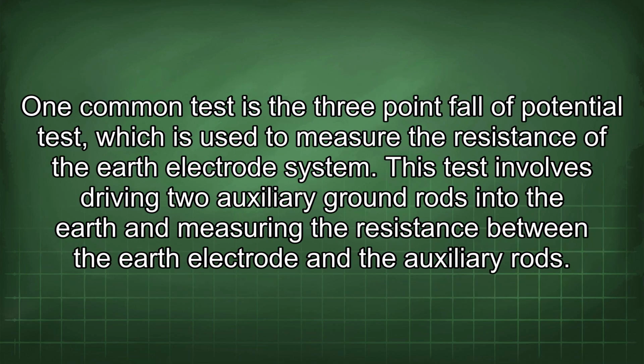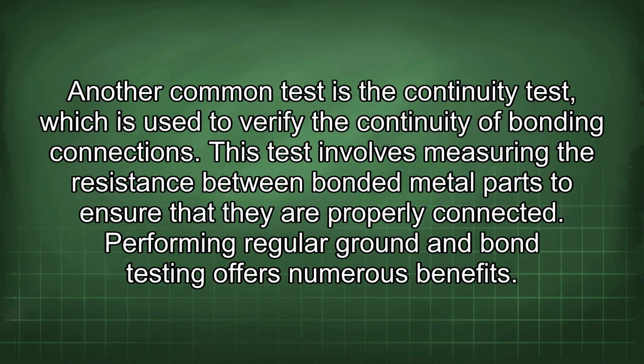One common test is the three point fall of potential test, which is used to measure the resistance of the earth electrode system. This test involves driving two auxiliary ground rods into the earth and measuring the resistance between the earth electrode and the auxiliary rods. Another common test is the continuity test, which is used to verify the continuity of bonding connections. This test involves measuring the resistance between bonded metal parts to ensure that they are properly connected.